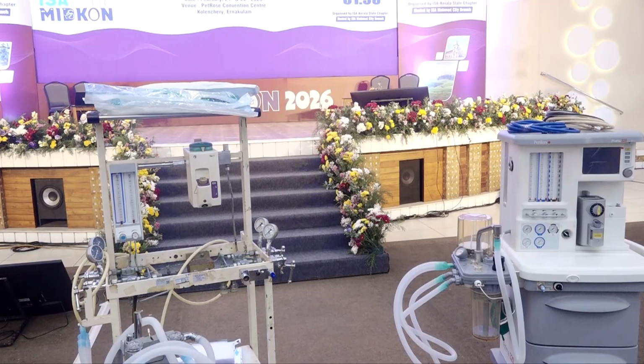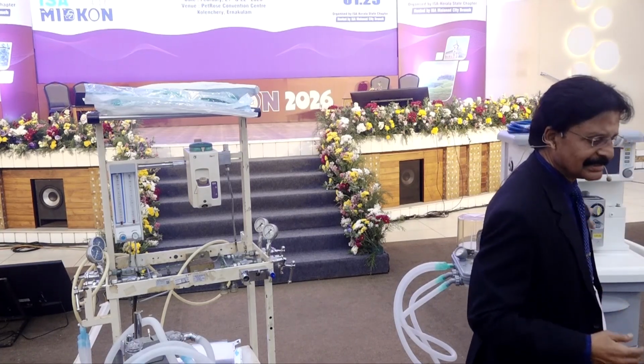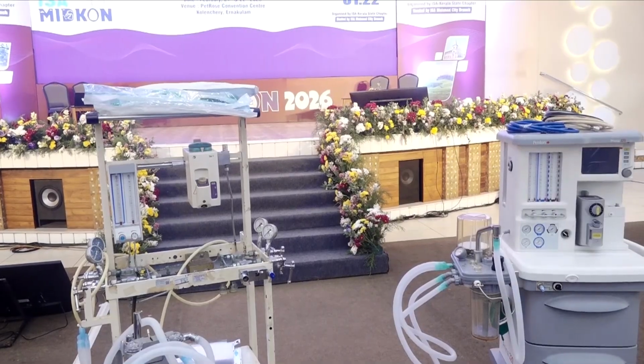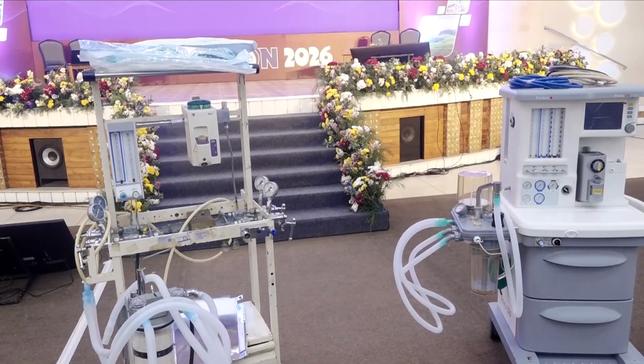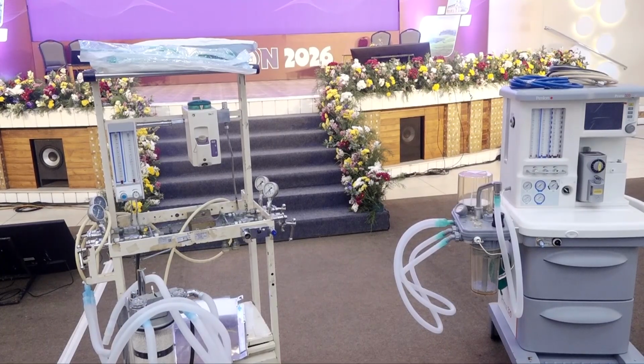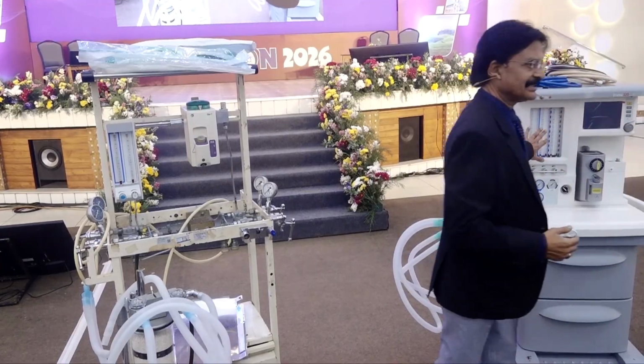Second stage pressure regulators. Whereas with Draeger, you don't have a second stage pressure regulator, what you have is a flow restrictor. What they have done in some of the Draeger machines is, as the gases come through the tubing into the flow control valves, they are narrowed. When gases pass through the narrowed portion, what will happen? Bernoulli's principle. The velocity increases, the pressure drops. So automatically, instead of a second stage pressure regulator, they have reduced the cost. So the pressure automatically reduces by the time it reaches the flow meter assembly.